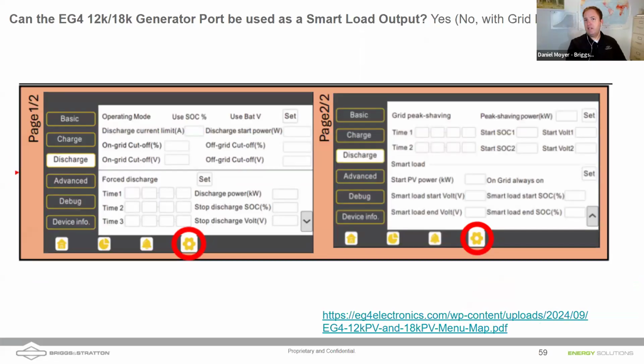The 18K PV, as I pointed out, has that, and the 12 has a third port, the gen port. It can be used to bring in a generator, AC coupled solar, or it can be used as a smart load output. Notably, though, if you're going to use the FlexBoss Grid Boss, and you can actually use the 12K and 18K PV with the Grid Boss, the smart load output cannot be used. You've got to use the smart load outputs inside of the Grid Boss.